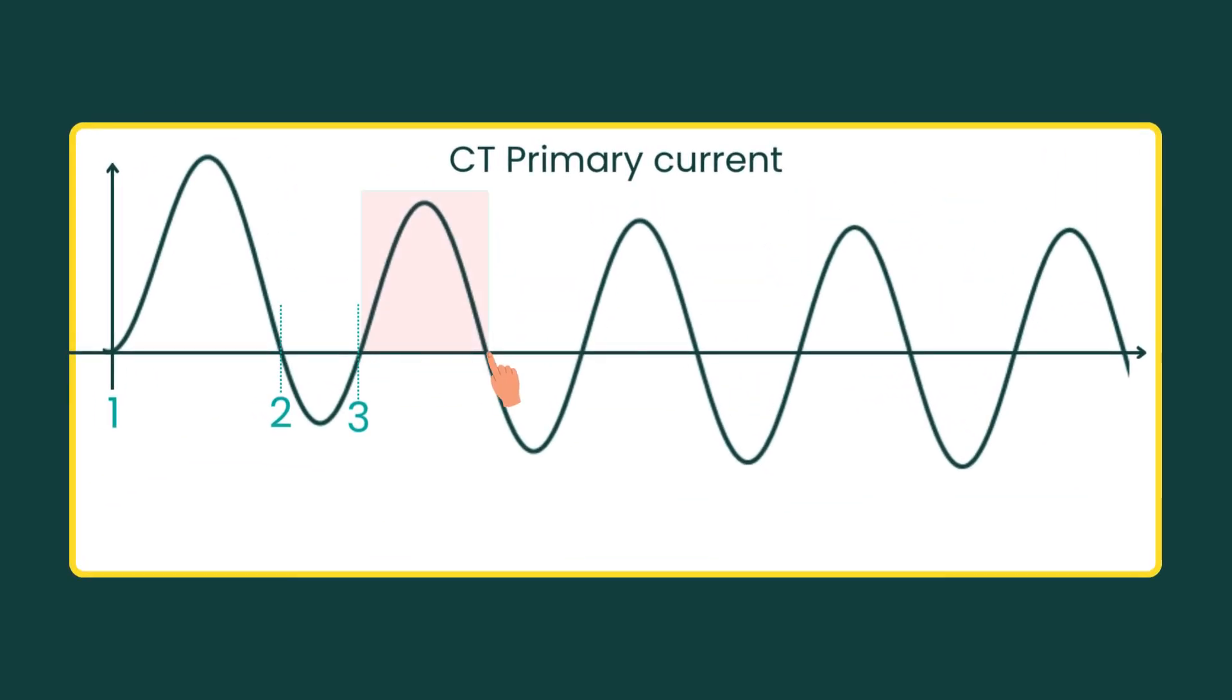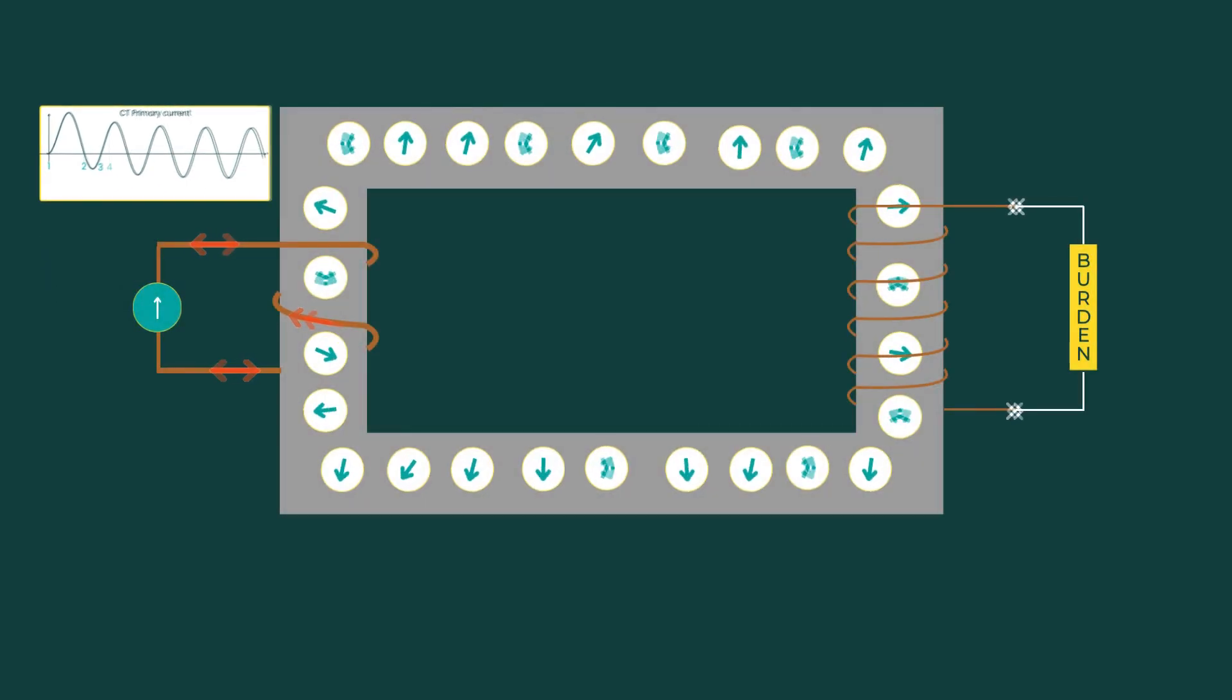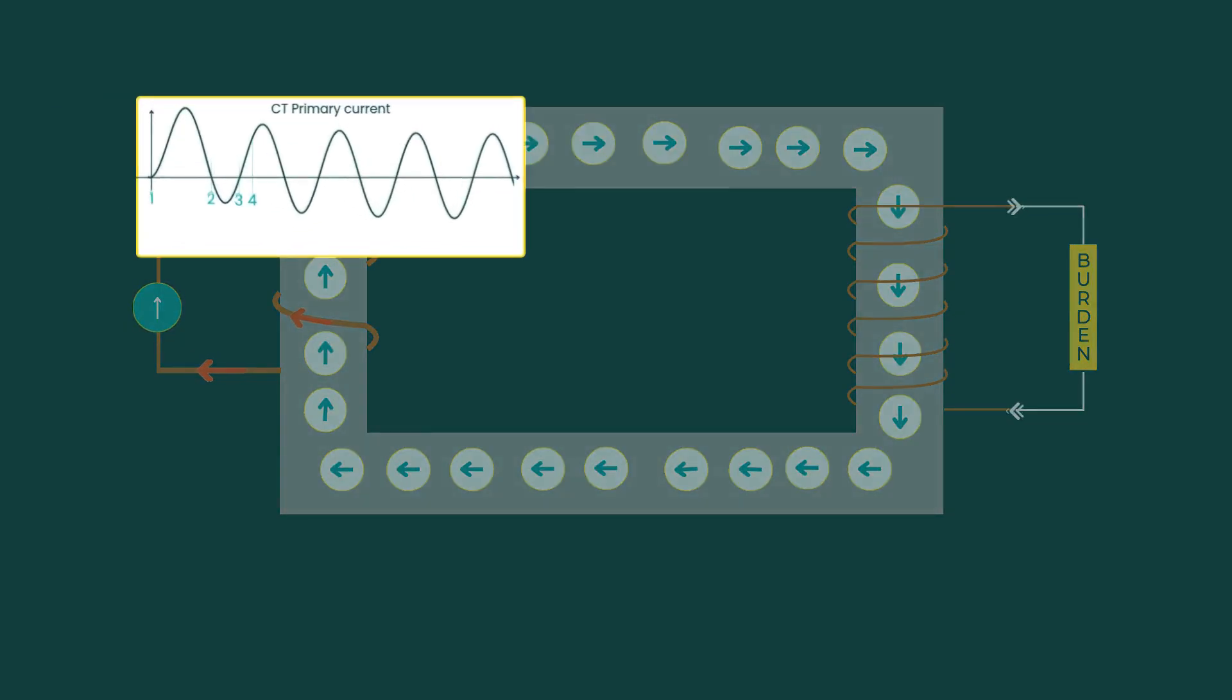In the second positive half cycle, the current continues aligning dipoles in the positive direction. But this time, before the half cycle ends, say around 0.4, all the dipoles become fully aligned. The core hits its magnetic limit. The CT saturates. Now the magnetic flux cannot change further, and the secondary current drops sharply. This is called asymmetrical saturation.